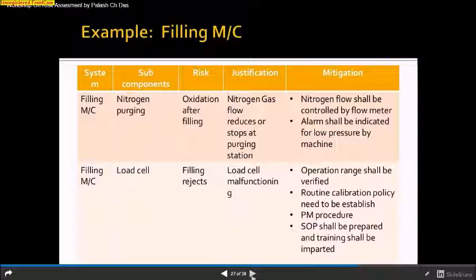When you are talking about the load cell, it should cover the operating range, and calibration should be established, and you should check whether the range needs to be calibrated. Your use range should always be within the calibrated range, not outside the calibrated range. And a PM procedure needs to be established, an SOP shall be prepared, and training shall be imparted.